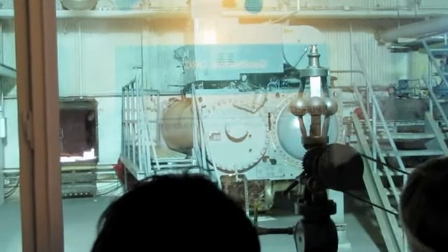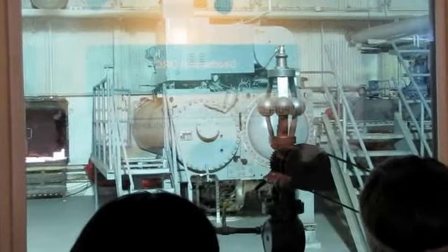Now if you take a look at these units, you can see they consist of two big tubes with the generator unit on top. If we could take the caps off of those tubes, what you would see is a big tube with a bunch of little tubes that go through the middle. Now the left side is our evaporator. We put our refrigerant in there, and then we run our hot water through all the little tubes. That hot water is hot enough to boil and steam the refrigerant, and it's the steam from the refrigerant that turns our turbines. It spins it at about 13,500 RPM. That goes through a reduction gear on the generator unit up top and spins that at...